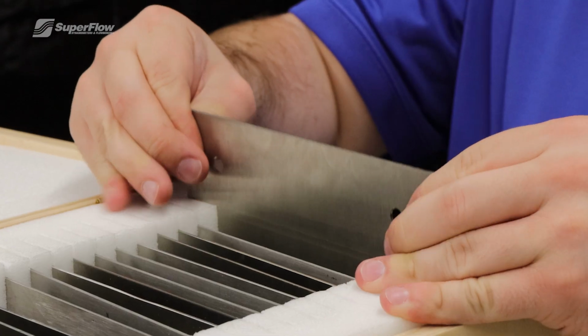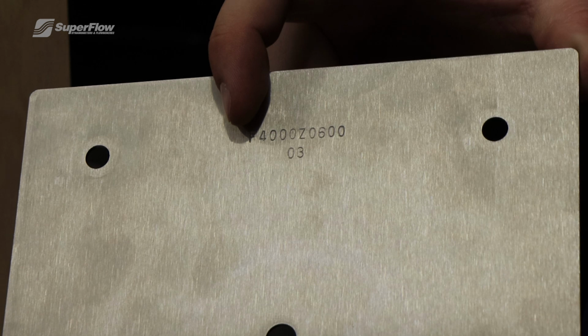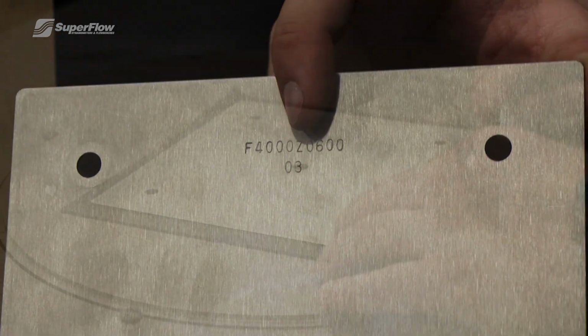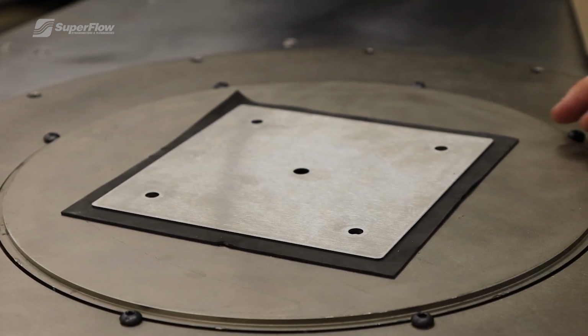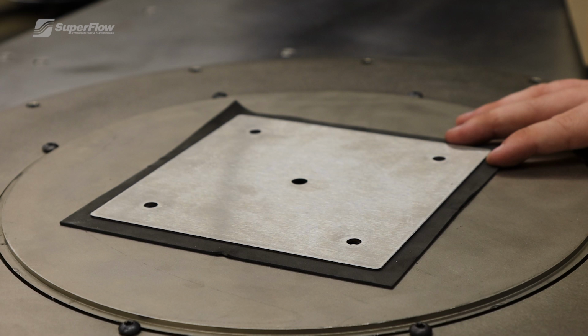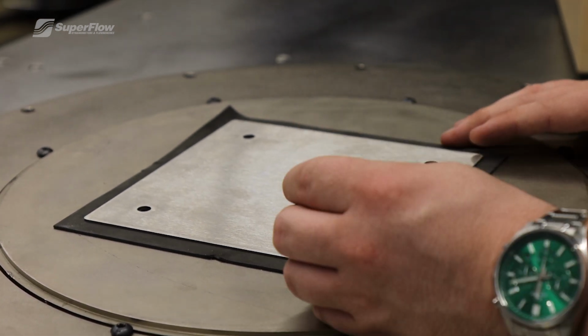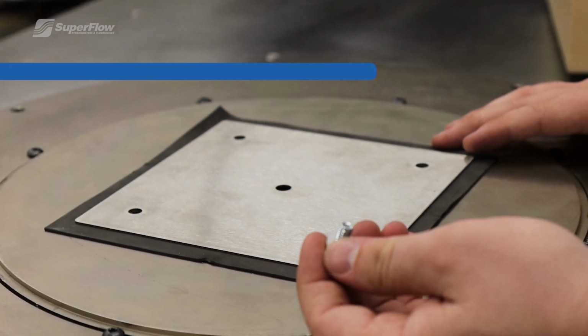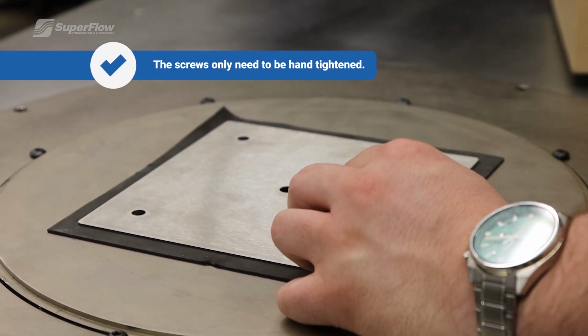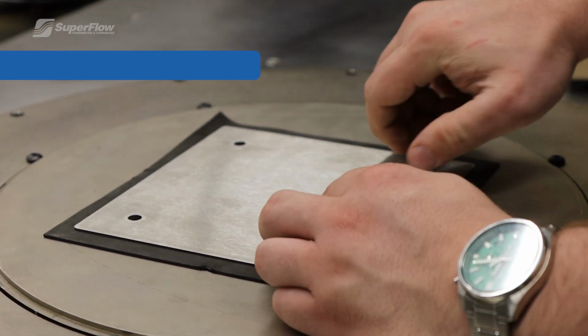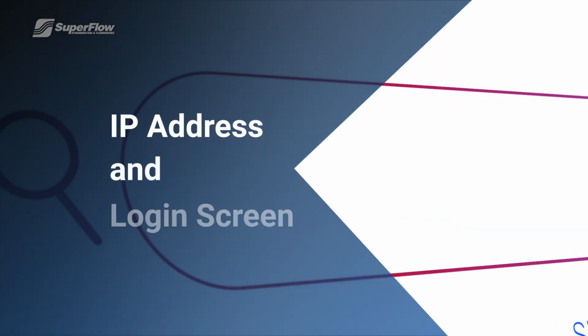So to start your calibration, you'll pull out plate number 3. The plates that will be utilized are number 3 through 16. Apply your plate to the orifice cover with the provided gasket, and you need 4 1/4 screws to tighten it down.